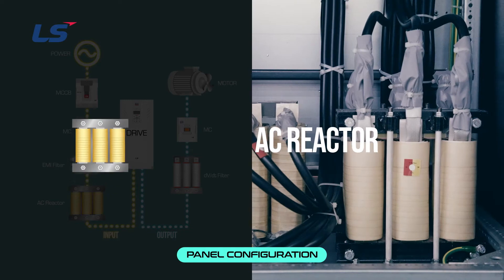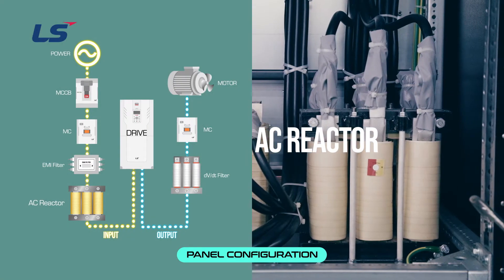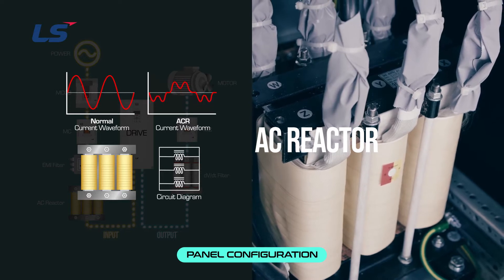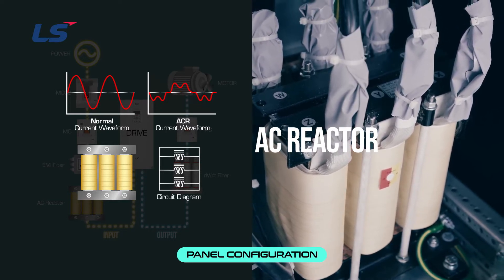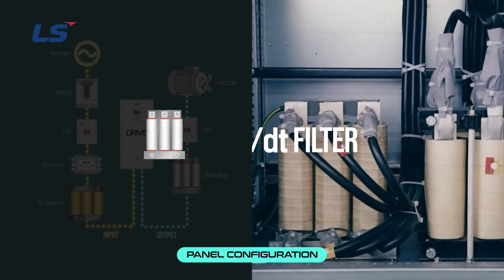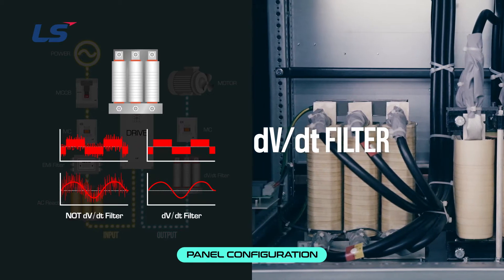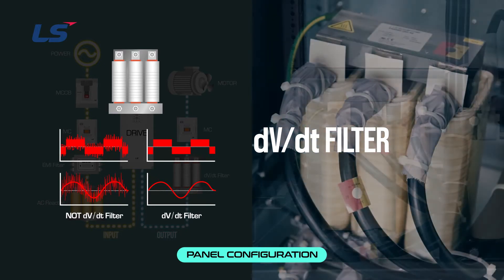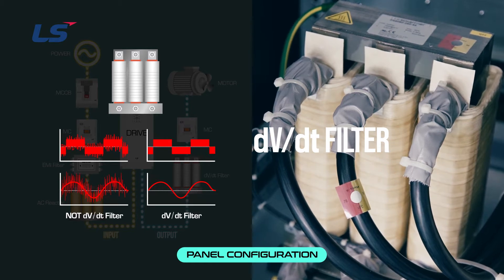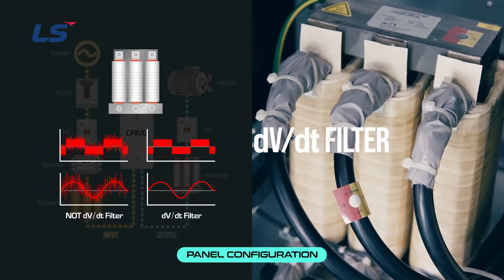The AC reactor is composed of reactors on the inside. It applies to the primary side based on three-phase rectification circuits. Compared to normal current waveforms, the waveform improves smoothly with the installation of the AC reactor. It also helps to suppress harmonic waves and improve power factor. The dV/dt filter is installed on the inverter output. It is a device that protects the motor from the transient surge voltage generated by the IGBT element inside the inverter. The waveform of voltage and current is improved depending on the filter installation. Installing the dV/dt filter extends the motor life and improves the reliability of the system.